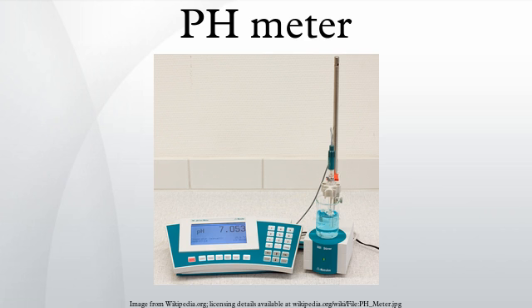As pH 7 is essentially a 0-point calibration, calibrating at pH 7 first, calibrating at the pH closest to the point of interest second and checking the third point will provide a more linear accuracy to what is essentially a non-linear problem. Some meters will allow a 3-point calibration and that is the preferred scheme for the most accurate work. Higher quality meters will have a provision to account for temperature coefficient correction, and high-end pH probes have temperature probes built in. The calibration process correlates the voltage produced by the probe with a pH scale.